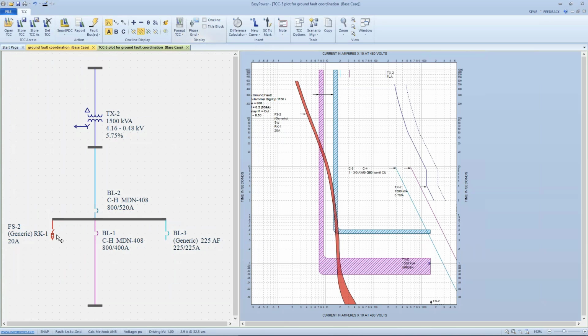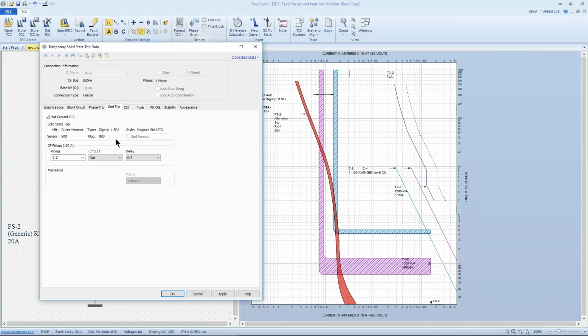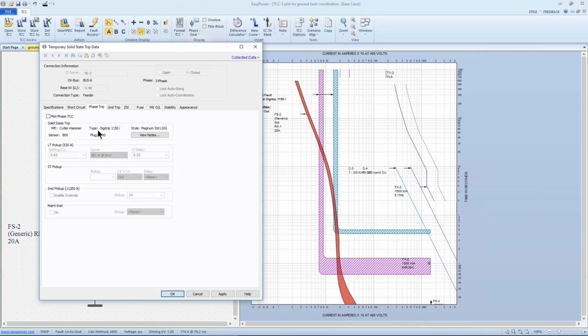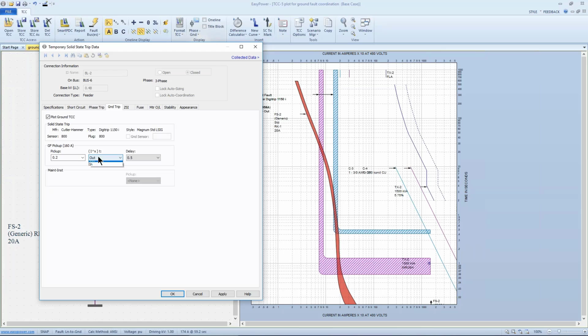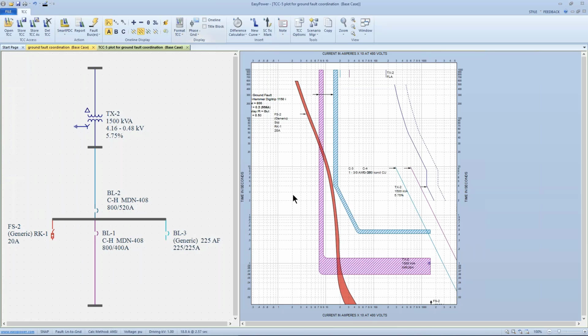Now, even though this breaker is downstream of the main, and it's in parallel with our feeder breaker downstream, it doesn't have to coordinate with the fuse, but we may want to coordinate our upstream main with the fuse protection downstream. So when that's the case, we can open up the trip curve, and for ground trip, put the I²T in, which puts this little corner protection in the curve and allows us coordination with the downstream fuse.